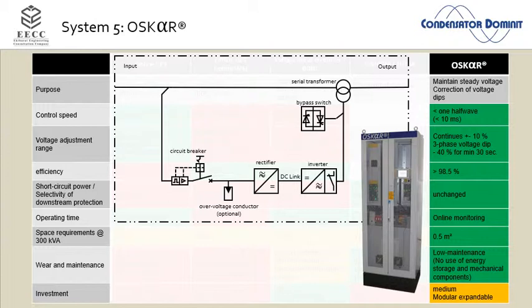This is the inverter here. It has only one goal in its life. The whole processor knows only one thing. If I measure a voltage drop here, the same measurement here, this inverter only knows one thing: my goal is to have the 400 volt, or whatever required output voltage, here. That's the only thing this inverter knows about the world. My job is to make it 400 volt or 500 or whatever I give to the software here.